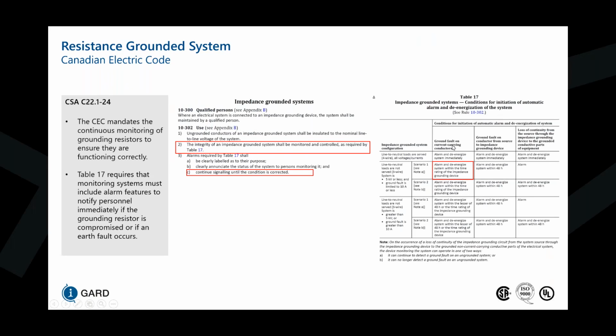And ground faults in the system are just to understand that there's a ground fault being picked up, and that's usually picked up with elevation in neutral voltage, as well as current flowing through the neutral. On the left-hand side here, you have impedance grounded system configurations. On the first row, it says line to neutral loads are served. I highly recommend that you just delete this row from your mind completely, because it's not recommended to distribute a neutral in a resistance grounded system. And each of the three cases indicate that you have to alarm and de-energize the system immediately.